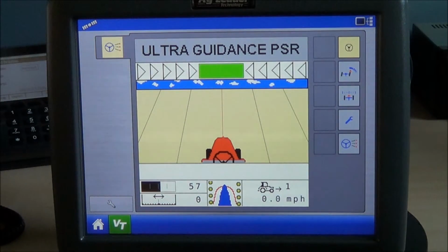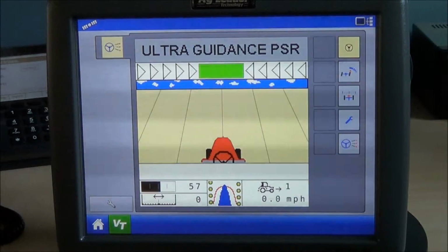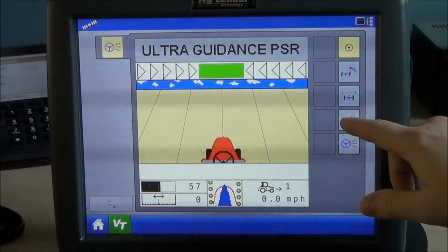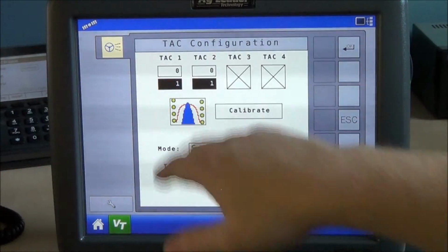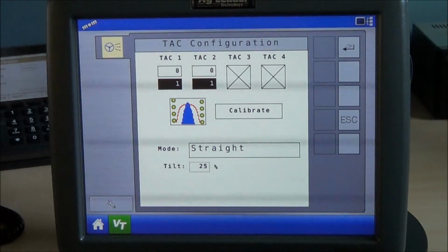From an operator's perspective, the important thing to know here with this system is how to calibrate the sensors. The paddles themselves have memory, and to do this calibration, I would say the first year, do this maybe once at the beginning of harvest, once the first week of harvest. You'll notice that these readings, neutral readings, will actually change over time just because of the natural memory in the paddles.